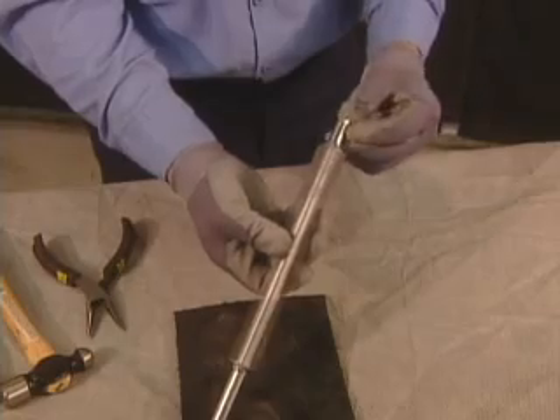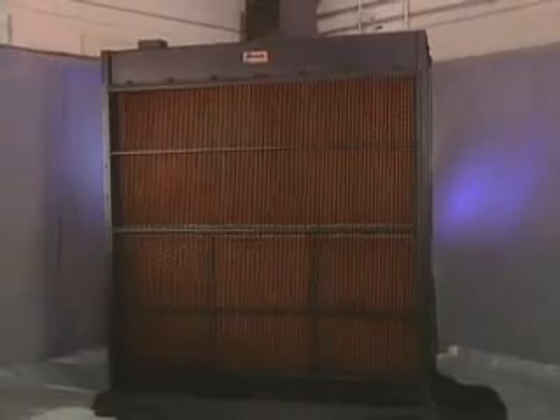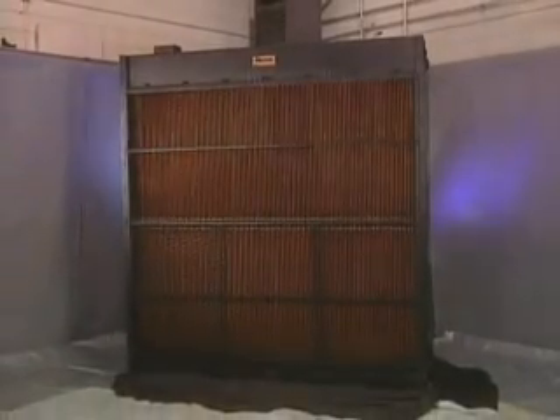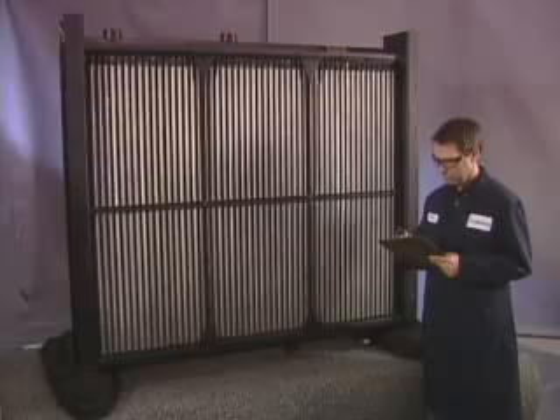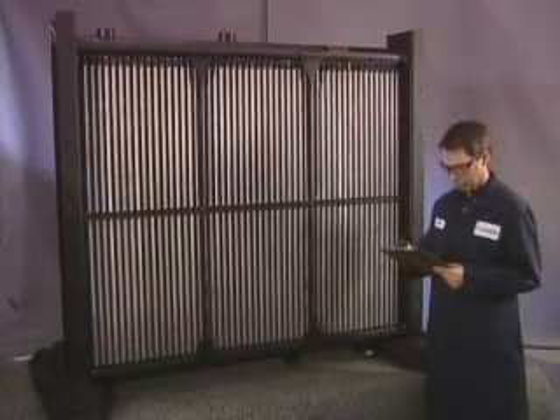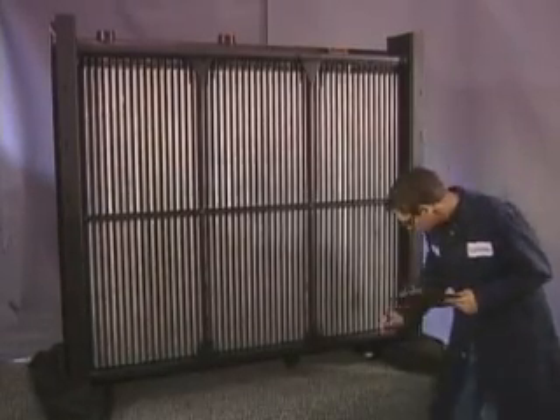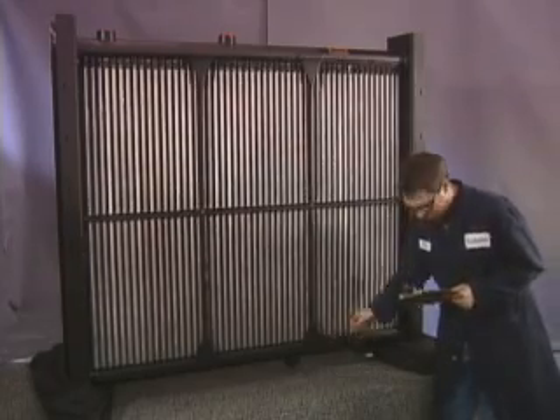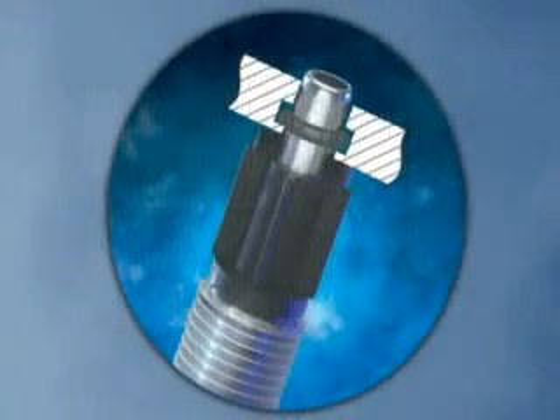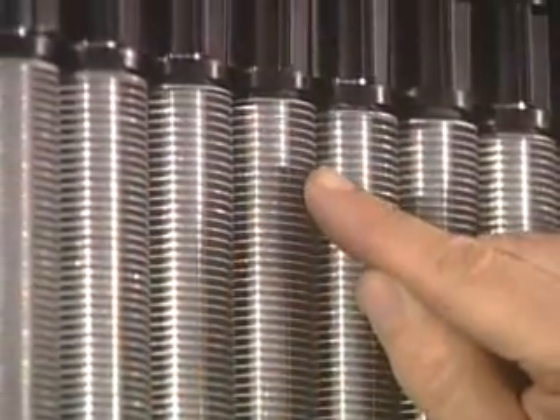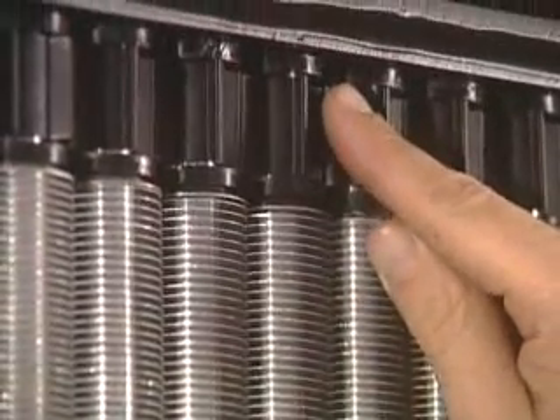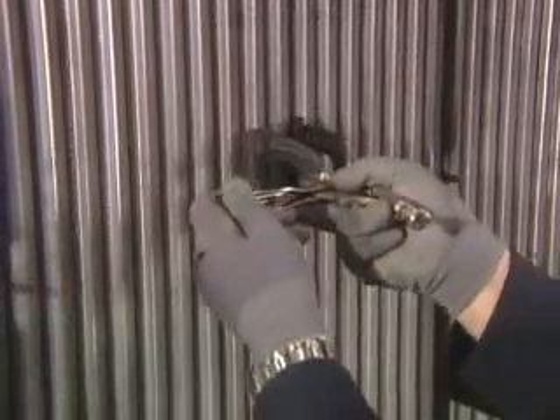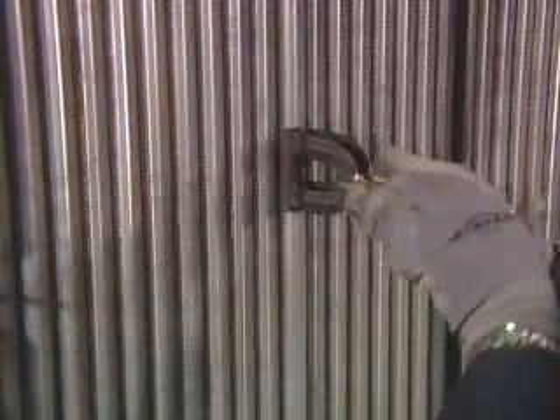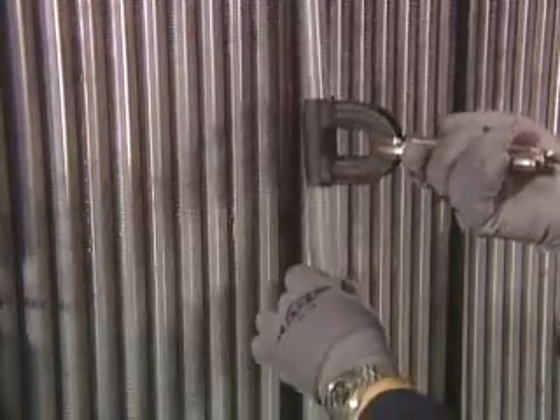Turbulators are placed in tubes to increase heat transfer. Where space is at a premium, high-efficiency copper tube oil coolers are available. For pressures exceeding 150 psi, L&M offers two CSC models that feature tube-to-header seals held captive in the header plate. Once a tube is in place, the seal is compressed to make a tube-to-header seal, capable of withstanding operating pressures to 500 psi. CSC coolers dismantle and reassemble for routine maintenance, much in the same way as other Mesabi products.